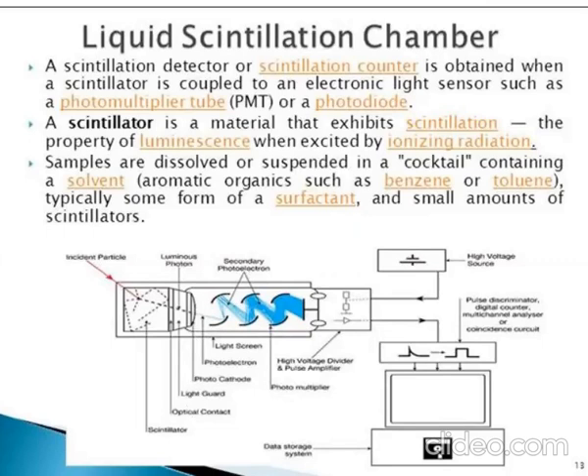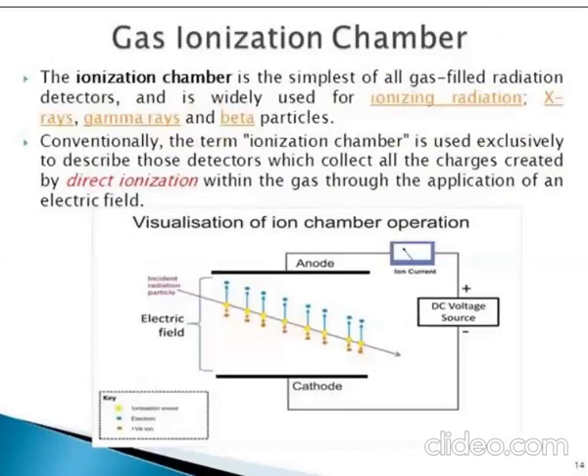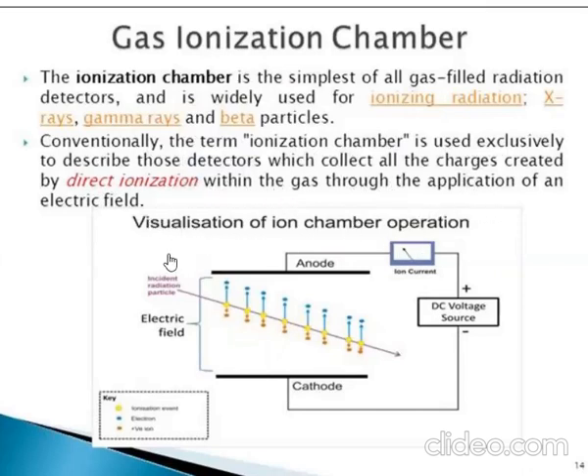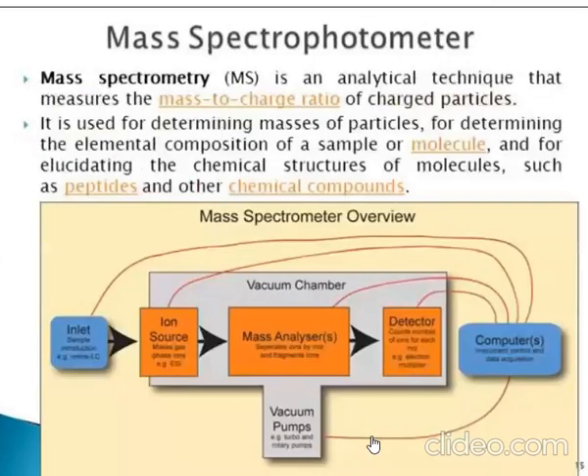The gas ionization chamber is the simplest of all gas radiation detectors and is widely used for detecting ionizing radiation — X-rays, gamma rays, and beta particles. It is used exclusively to describe detectors which collect all charges created by direct ionization within the gas through the application of an electric field. In operation, incident radiation between the anode and cathode with a DC voltage source produces a current that can be read as a measurement.